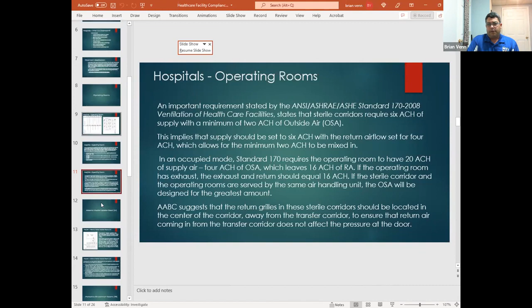Standard 170 requires that the operating rooms have 20 air changes of supply air, and they're looking for 4 of those air changes to be outside air, and that leaves 16 of them on the return. So if your test and balance companies are only giving you a test and balancing report on pressure rooms and air change per hour measurements, and it's only reporting the supply on positive rooms, then you may not be capturing the return air and understanding how many air changes of outside air will be coming into that room.